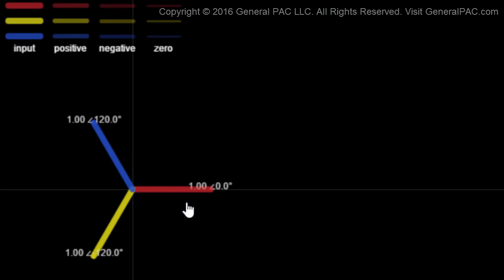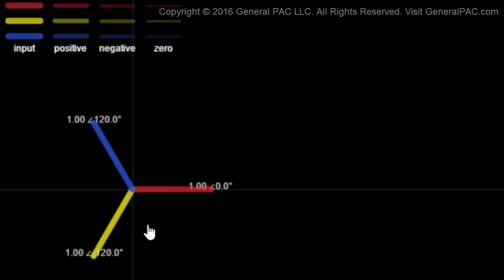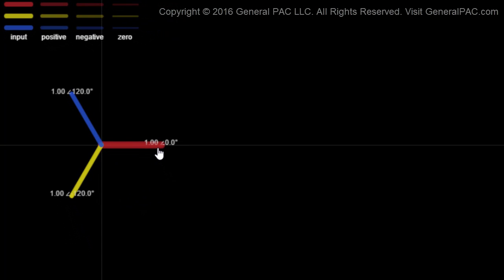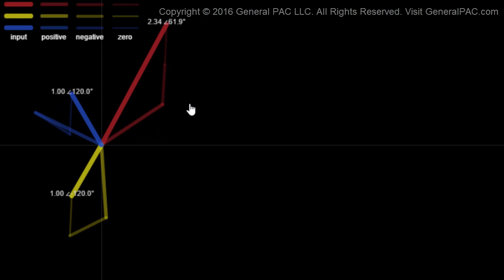Now let's look at a different perspective. I've superimposed the symmetrical components onto our system phasors directly to look at the characteristics of symmetrical components that way. Because this is a balanced system, we would only get the positive sequence component, and it would look exactly like our balanced system. Now as soon as we change phase A current, we get a decomposition of symmetrical components — meaning the symmetrical components equal our unbalanced system. This was phase A positive sequence component, this was phase A negative sequence component, and this right here was phase A zero sequence component.